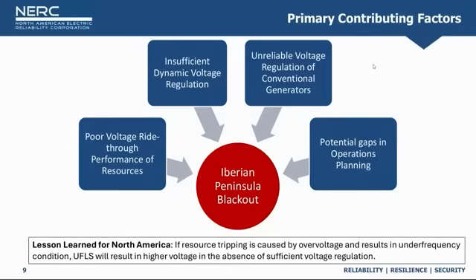We also saw insufficient dynamic voltage regulation. Spain relies solely on the operating conventional generators for dynamic voltage regulation. That's different than what we have here. Spain's policies do not require the IBRs to provide dynamic voltage support. Most operate at a fixed power factor, which means that when generation is curtailed during overvoltage conditions, the IBRs are not allowed to manage voltage. The system loses its ability to control reactive power.